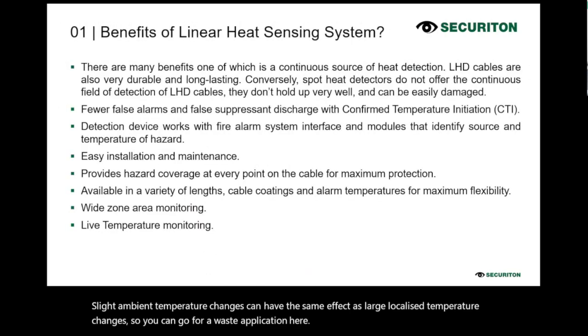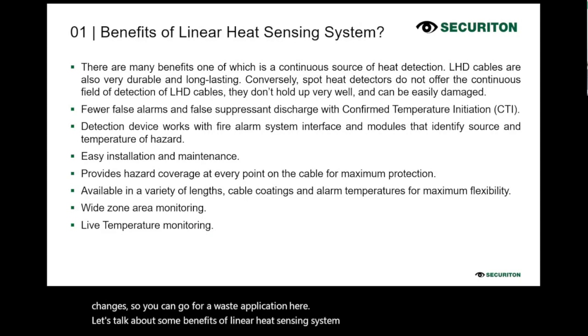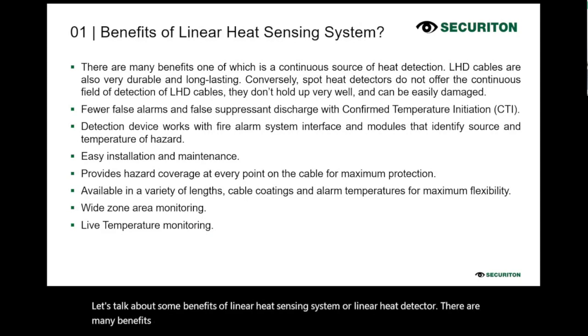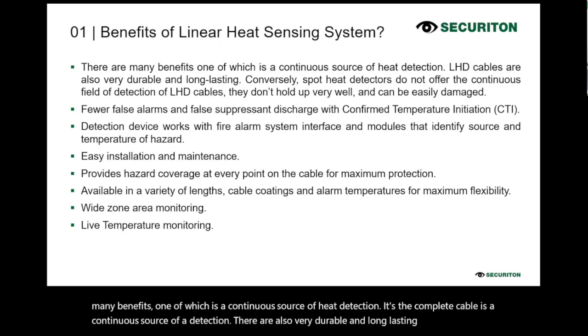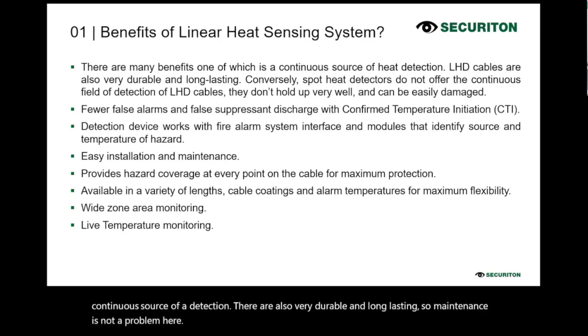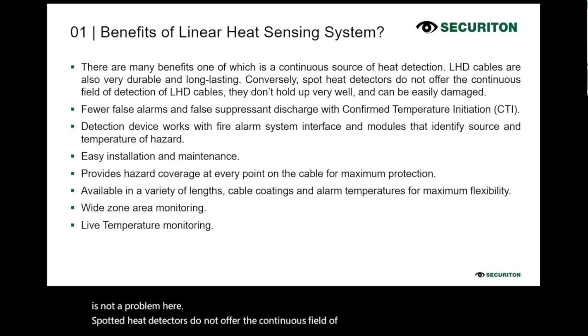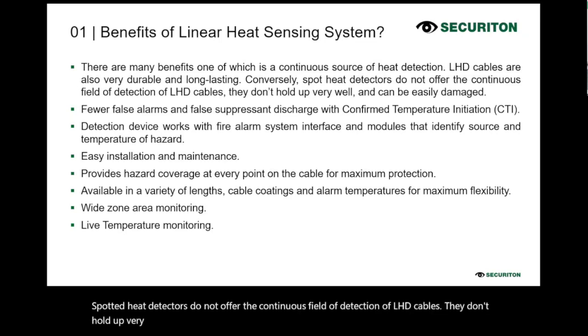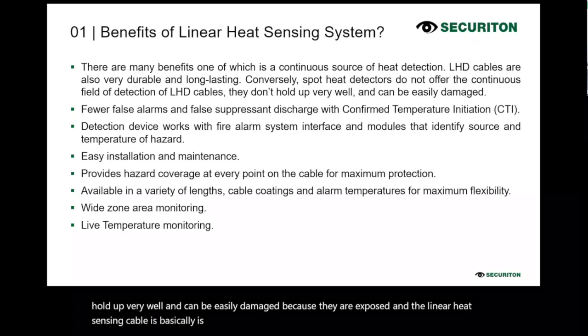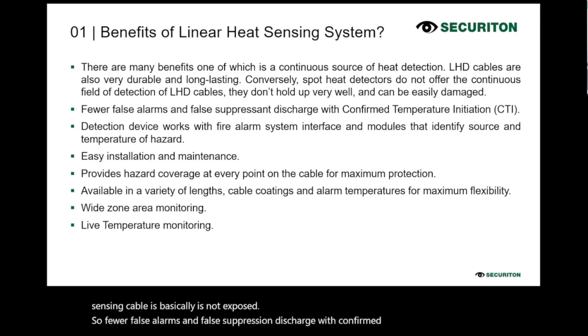Let's talk about some benefits of the linear heat sensing system or linear heat detector. There are many benefits, one of which is a continuous source of heat detection. The complete cable is a continuous source of detection. They are also very durable and long lasting, so maintenance is not a problem here. Spot heat detectors do not offer the continuous field of detection of LHD cables. They don't hold up very well and can be easily damaged because they are exposed, whereas the linear heat sensing cable is not exposed. So there are fewer false alarms and false suppression discharges with confirmed temperature initiation.